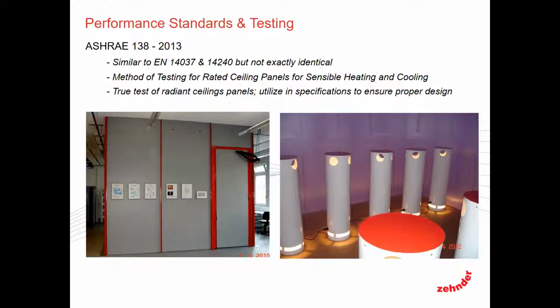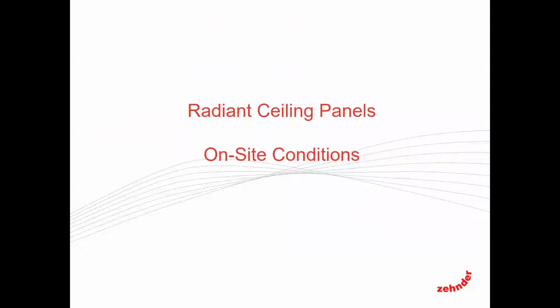So it's very important. So now, when you come to a manufacturer, or at least when you come to us, I'll say it that way, you ask us for performance, we're going to give you the performance based upon the standard. So if the standard produces, and I'm just going to pick a number, 35 BTUs per square foot based on your design conditions, that is what we're going to size the system, the active area, on. That'll be the number that we would use.